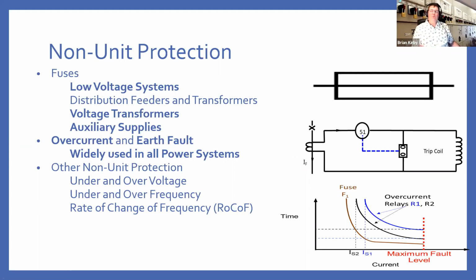On voltage transformers, you will have a fuse as well, and some auxiliary supplies. As a fuse works, if the current exceeds a certain level, the fuse will burn out and break the circuit. Of course, the problem with that is you then have to manually go and replace the fuse to re-energize your system. So overcurrent and earth fault protection devices were developed.